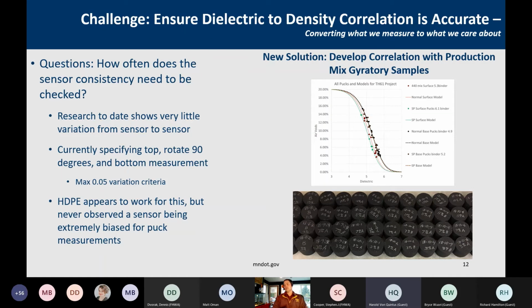So we still have to answer the questions. We can't just say it's very consistent from sensor to sensor, test to test. So the question is, how often do we have to do our repeatability tests? Right now, we're just doing every single specimen: measure the top, rotate it 90 degrees, measure the bottom, and make sure it's within 0.05 dielectric. The high density polyethylene appears to work for this, although I'll say we have less data of sensors being out of spec with this method, so we can't necessarily say just because it's within spec for HDPE that it's going to be in spec for the asphalt samples as well. So just something to consider.